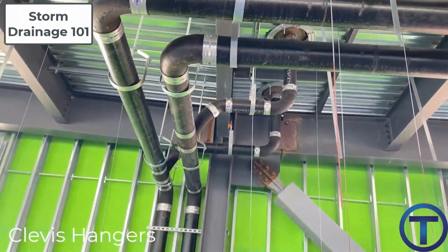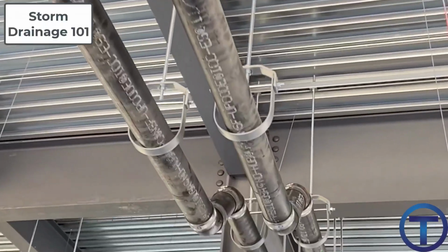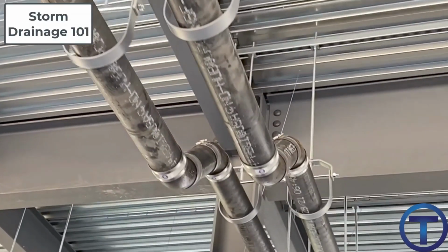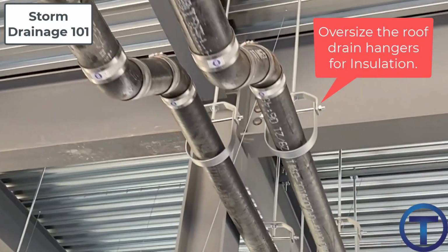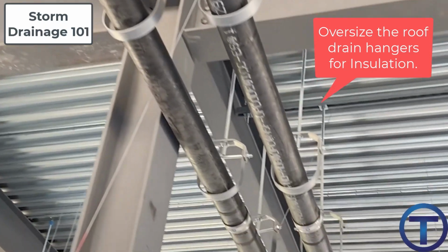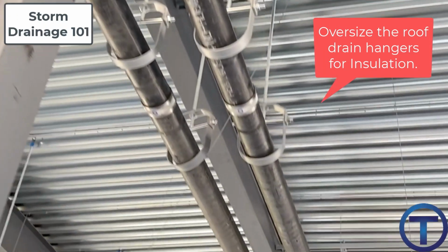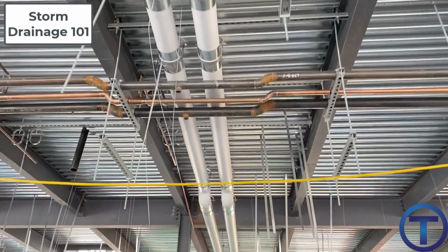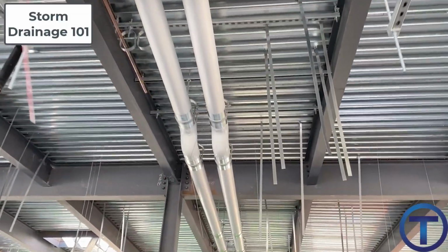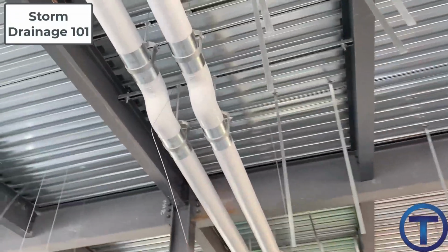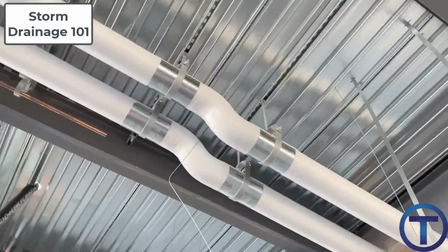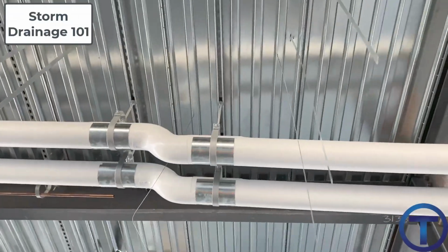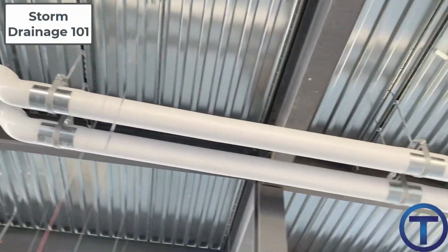But it's also an important thing to note, when roof drain Clevis hangers are installed, you want to oversize those hangers big enough so that the insulation can be installed in the same hanger without having to redo the hangers after you've hung the pipe. An oversized Clevis hanger can be adjusted down on the all thread, making room for those insulation sleeves.